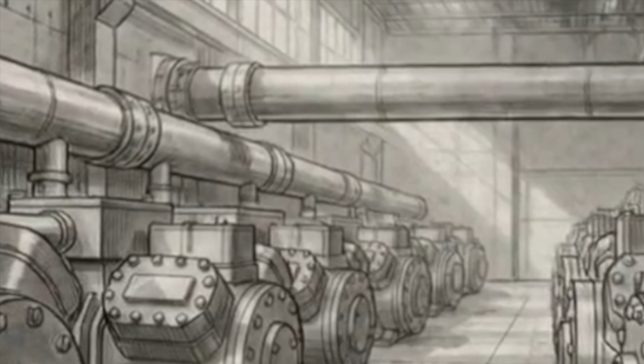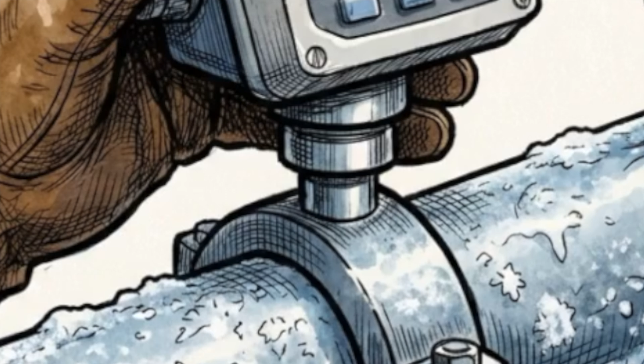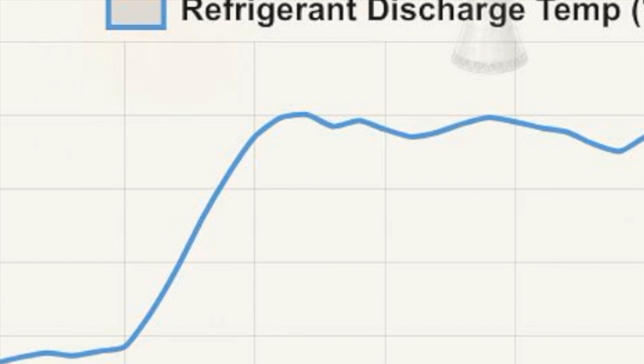You can prove this waste exists in any facility quickly. You walk in and pitch a free energy audit of their compressor room. You only need 48 hours. You clamp an ultrasonic flow meter and a temperature probe directly onto the chiller's discharge line. This gives you hard data on exactly how much thermal capital they bleed into the sky.